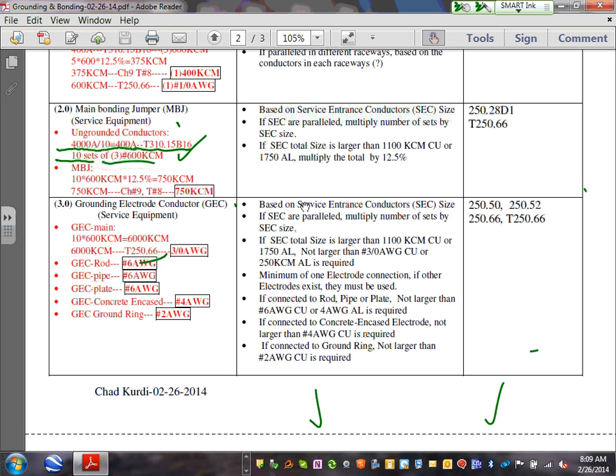310.16 under the 75-degree column, so it says. Then you take the 10, multiply it by 600 kcm, multiply by 12.5%, give you the 750. You take the 750, guys, to chapter 9, table 8, and that will get you that main bonding jumper. The main bonding jumper will be 750. Any comments, guys? Any questions about sizing the main bonding jumper at the service?